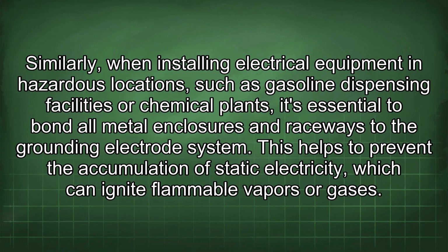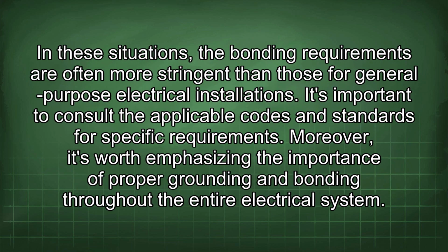Similarly, when installing electrical equipment in hazardous locations, such as gasoline dispensing facilities or chemical plants, it's essential to bond all metal enclosures and raceways to the grounding electrode system. This helps to prevent the accumulation of static electricity, which can ignite flammable vapors or gases. In these situations, the bonding requirements are often more stringent than those for general-purpose electrical installations. It's important to consult the applicable codes and standards for specific requirements.